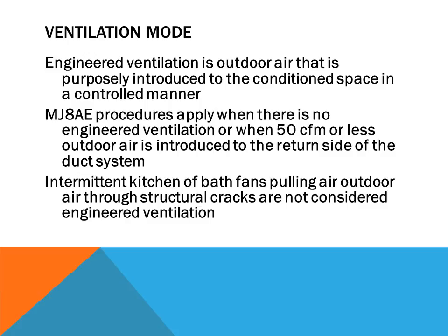So we look at the ventilation system and how we need to apply that to a house. When we have kitchen fans and bathroom fans that are actually drawing air out of the house, we need to replenish that amount of air through other means. If you can control it somehow by having a ventilation system, we can control that to a certain point, because if the house is tight and we mechanically bring air into the house, we can control the amount of infiltration and exfiltration based on when the temperature is extreme, and make the house more efficient that way. So we have to have a house with some air changes and it cannot be extremely tight, so you have to have some ventilation. But the more you consider controlling by mechanical means, the more efficient the house will become.